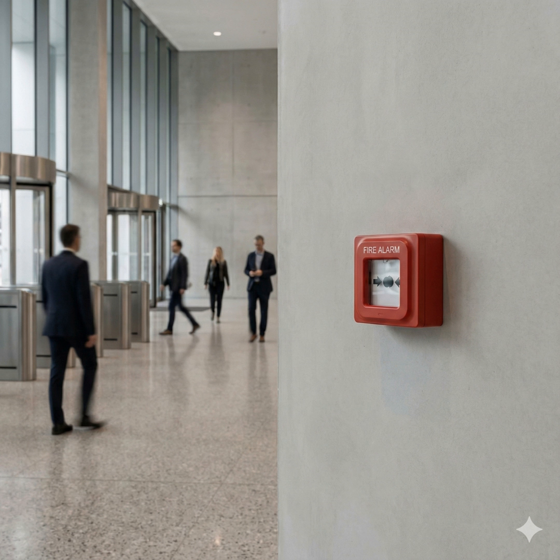That's the whole point. And finally, let's revisit the high ceiling problem with an architectural solution. Beam smoke detection. Beam detection is for horizontal coverage over extreme distances, from 15 to 100 meters or more. A transmitter sends an IR beam to a receiver, and if a smoke plume obscures that light path by a certain percentage, it reports a fire.